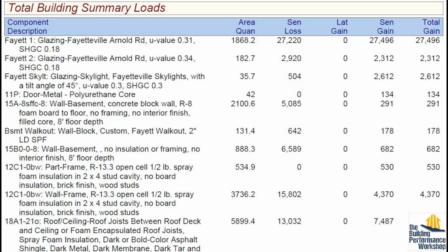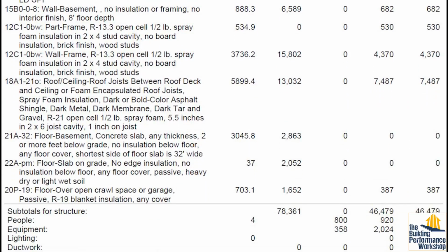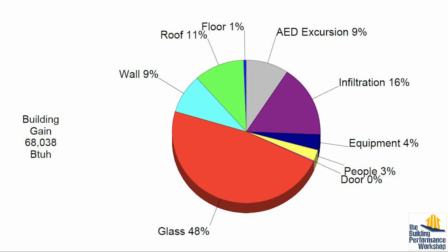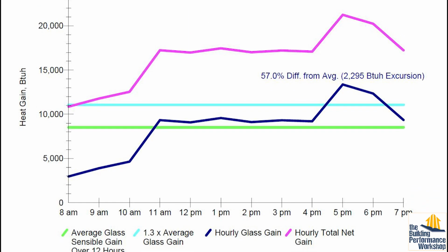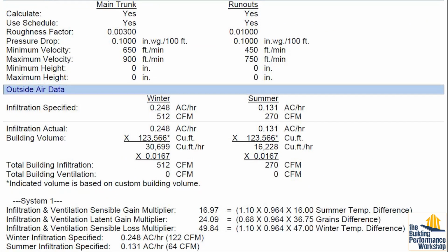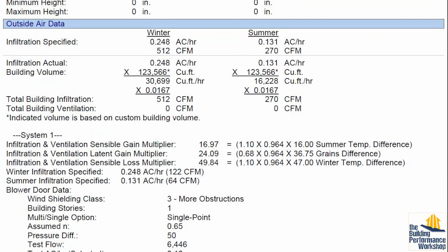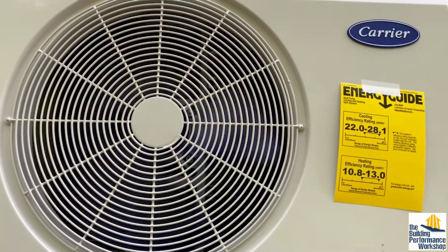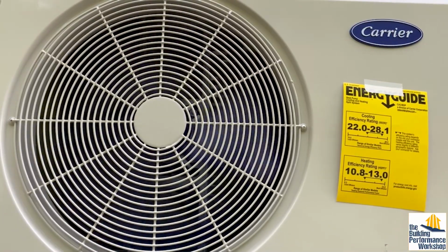Where we used to throw 1 ton of cooling at each 500 square feet or so, a new or improved home today only needs about 1 ton per 1,200 square feet. But don't trust that number either, because rules of thumb don't work. You almost always need a computer to calculate the heating and the cooling loads. And yes, it takes time to measure and input the insulation and window stats and the blower door test results, but it's important. Also, the capacity on the system label is not always reality.